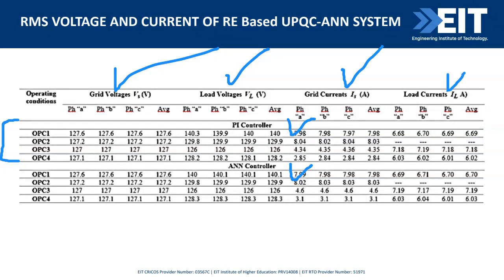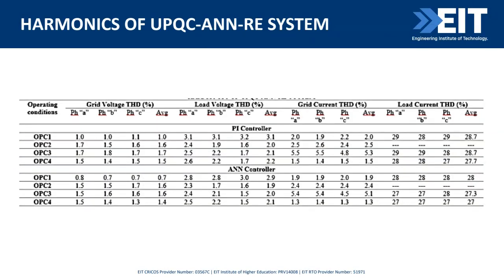And these were the harmonics noticed for every operating condition against every grid voltage, the total harmonic distortion, or THD, concept. This is a very common concept used on the power quality side. It relates to investigating harmonics, looking at the distortion, and finding possible ways to bring it down. So load voltage, grid voltage, and load current harmonics were all obtained. I'll show you the graphical depiction in the coming slides so you get a clearer idea about this technical data.